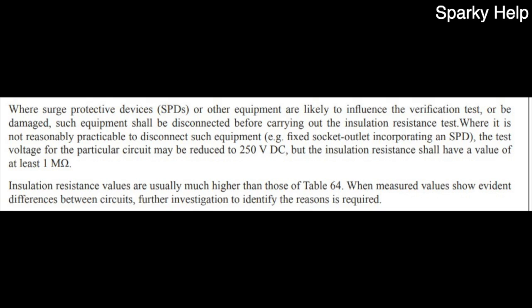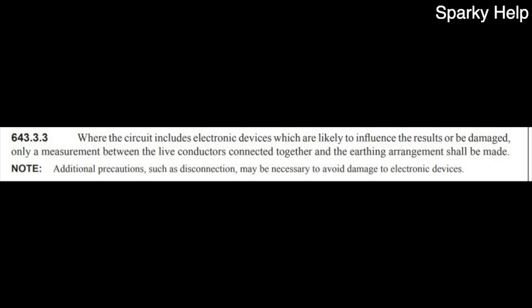So if we do have surge protection connected, then what we can actually do is lower the test voltage if you think that equipment is likely to influence the verification of the test, as this regulation says, or that you might damage it if you cannot remove it. So let's lower it to 250 volts. However, bear in mind that the minimum insulation resistance should still be at least 1 megaohm. Regulation 643.3, where the circuit includes electronic devices which are likely to influence the results or be damaged, suggests we can connect live conductors together, remember that's line and neutral, and then test those two down to earth. Note, it does say additional precautions such as disconnection may be necessary to avoid damage to electronic devices, but remember, this is your responsibility.